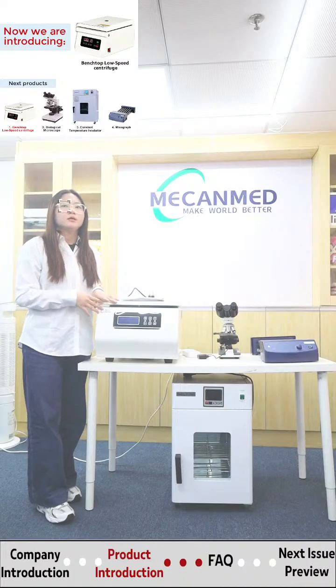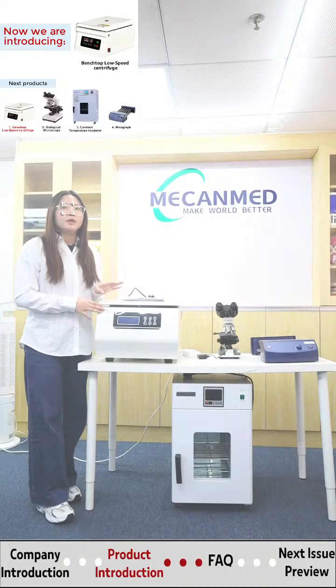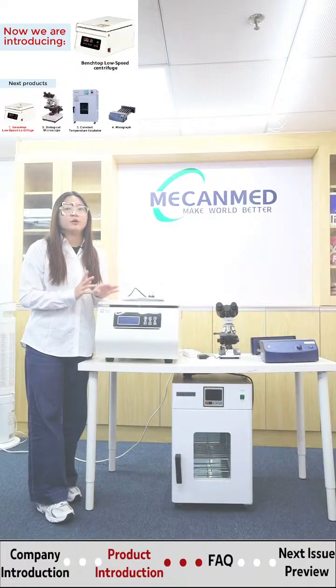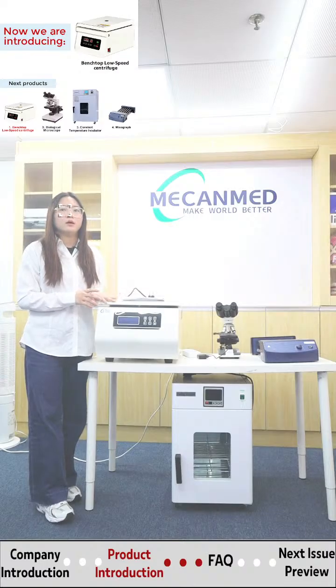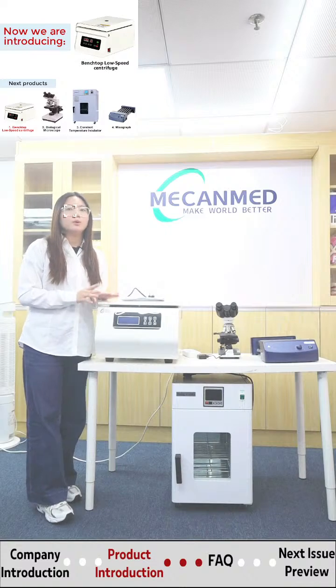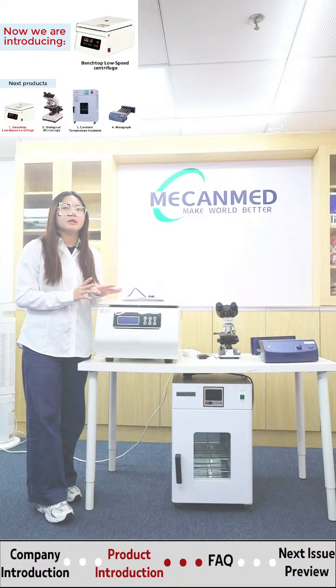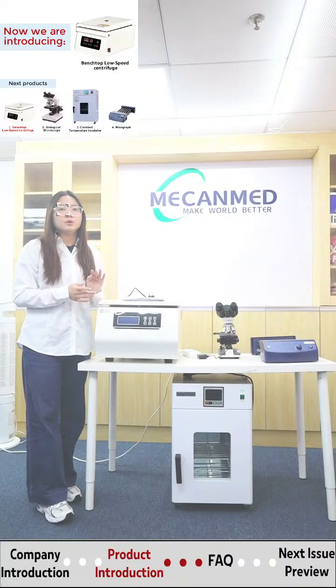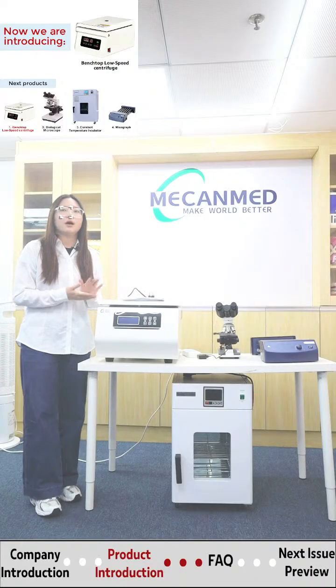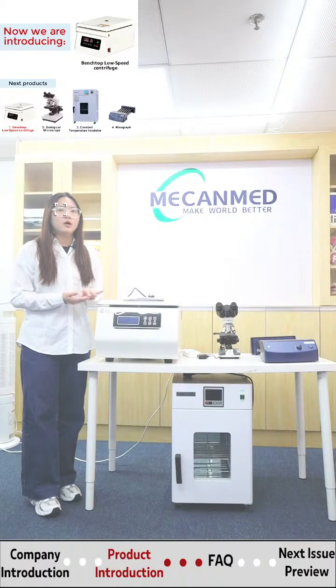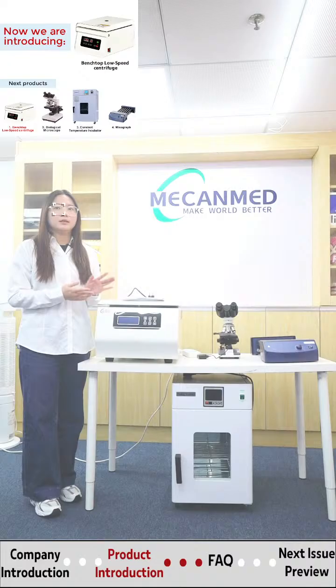Okay, next, the robust safety features. It has a balanced status protection device. That means if your samples are unbalanced, the centrifuge won't run, preventing any dangerous vibrations or damage. Plus, there's a safety switch and a mechanical door lock. The door won't open until the centrifuge has completely stopped, so you don't have to worry about accidental contact with moving parts. Okay, let me quickly show you how easy it is to use.